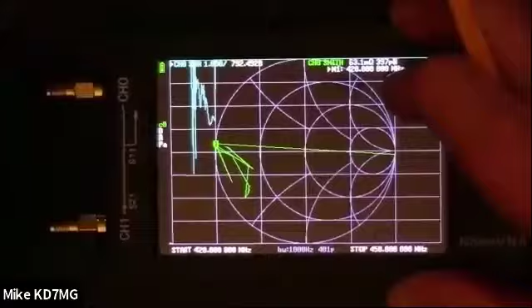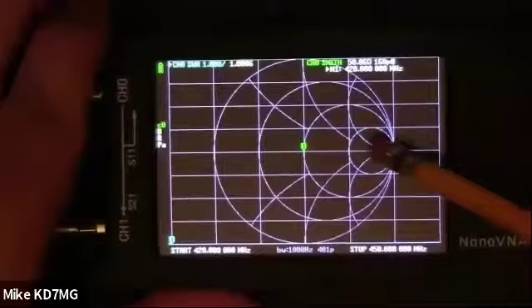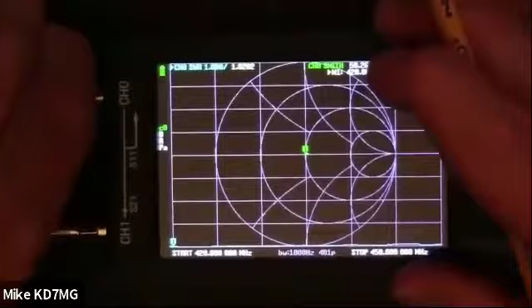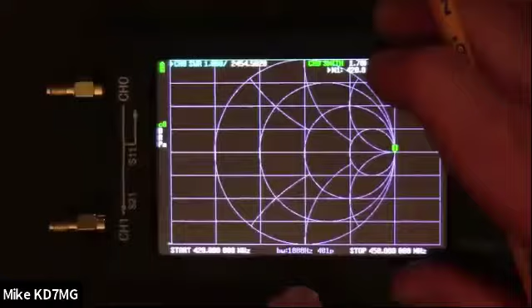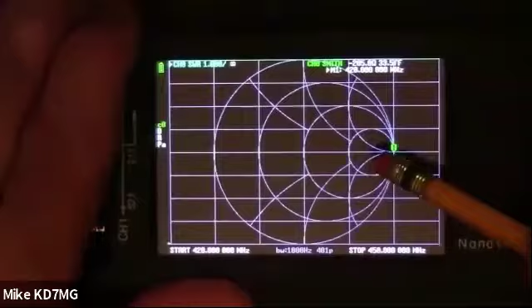If we remove it, at these frequencies, there's not much difference between the open standard and the open circuit without the standard. Very tiny phase difference there. And this is a 50 ohm load. Those 3 data points are the only ones that you need to calibrate. I wanted to show those familiar with the Smith chart that we were still calibrated even though we had changed our frequency range. This program, the firmware, knows how to interpolate between points very well.